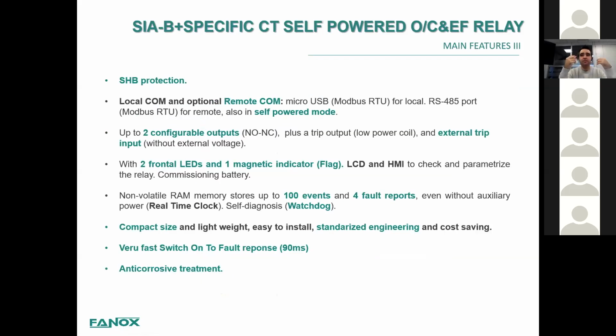One important thing that this relay has is a second harmonic block protection. This is something that is not very common on this kind of relays, but it's very important, and it's becoming more and more important as the size of the turbines and the solar inverters is becoming bigger and bigger. So the inrush current during the energization of the transformer is becoming higher. In this situation, it's very important to distinguish when there is an energization of the transformer and when there is an actual fault. With this protection function, based on the detection of the second harmonic on the current wave, we can distinguish these two situations and avoid unnecessary tripping during connection of the transformers.